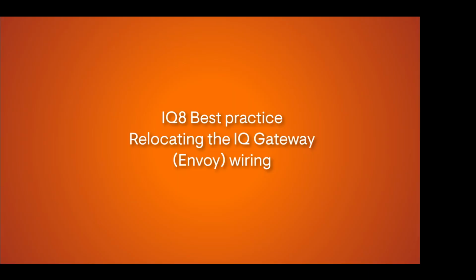The next critical best practice for installing IQ8 microinverters in a backup system configured with a system controller is the power for the IQ gateway or Envoy has to be moved from being powered on the IQ combiner bus to run directly from the system controller bus. Not doing this could cause the system to not function correctly, and more importantly, could cause a failure of a system component in the system controller.